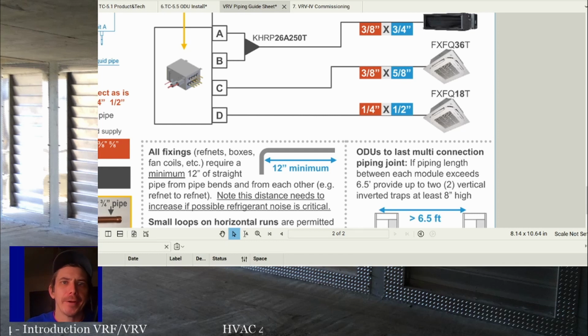I don't care if it's kind of ugly. You could have perfectly straight pipe with lots of nice neat 3/8 or half-inch elbows brazed in so it looks clean right up to the unit. Or it's going to be kind of ugly and bend up over and sideways and into the unit. Let it be ugly, and not have those extra joints where you can have a leak, and you'll have smoother, more gradual turns in the piping.